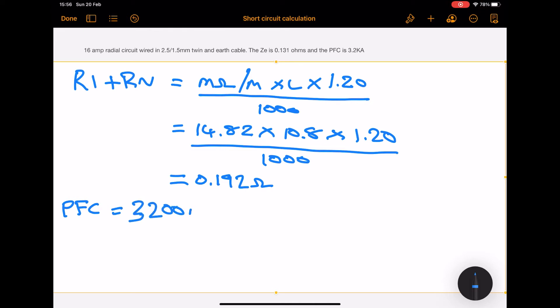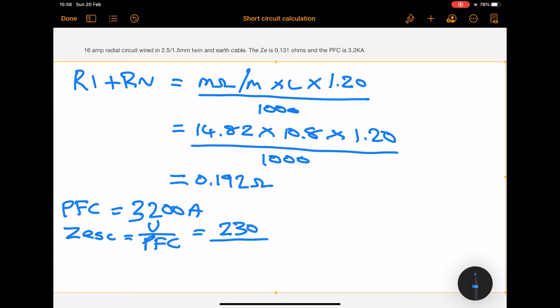Now for the short circuit calculation, we take the PFC which is 3.2 kA or 3200 amps and convert that into ohms. To find the ZESC — the ZE short circuit, which is the loop impedance between line and neutral — we divide the voltage by the PFC. So that's 230 volts divided by 3200, which gives us an answer of 0.071 ohms.